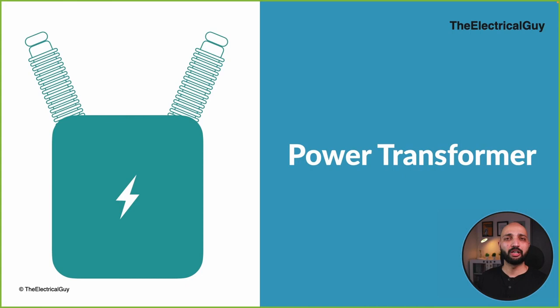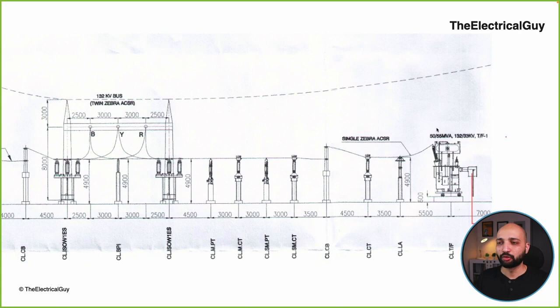Now let us move on and talk about the most expensive equipment in the substation, that is power transformer. So here is the most expensive equipment in the substation, and that is transformer. Now this particular transformer is 132 kV by 33 kV, which means it's a step down transformer. Now let us understand here the difference between 145 kV and 132 kV. Now 132 kV is the nominal system voltage which will normally remain in the system, and 145 kV is the rated voltage.